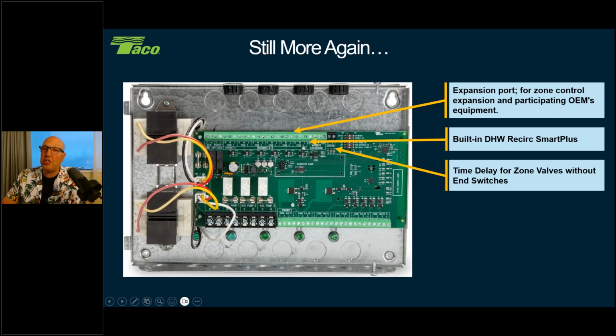In the dip switches here, again, very similar dip switches to the Dash 4, but the very last one, we added a setting for zone valves without end switches. All right, not a 4-wire zone valve. We're looking at a 2-wire zone valve. And we see a lot of that in our radiant systems and actuators.